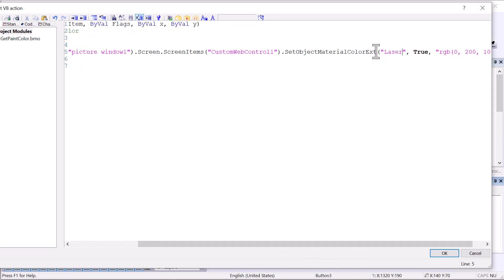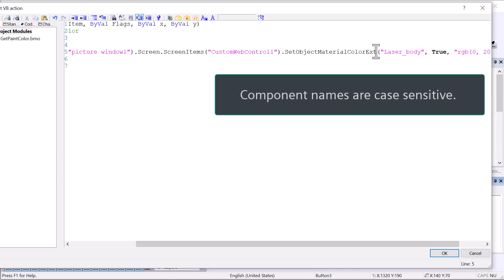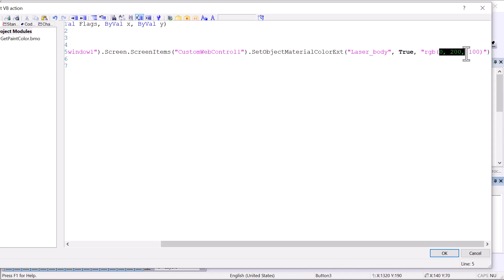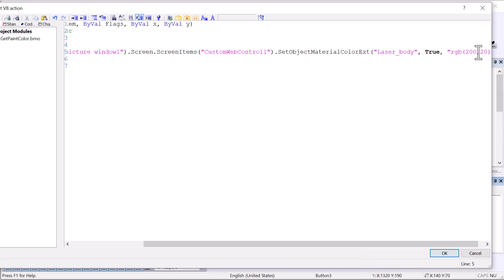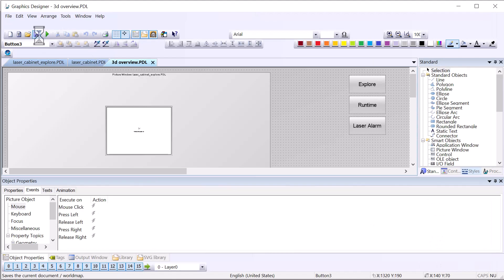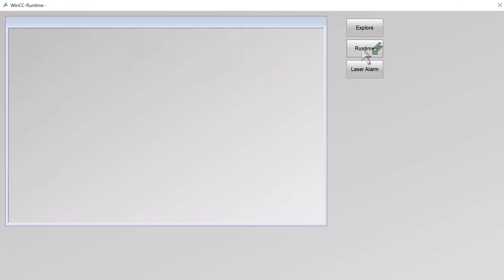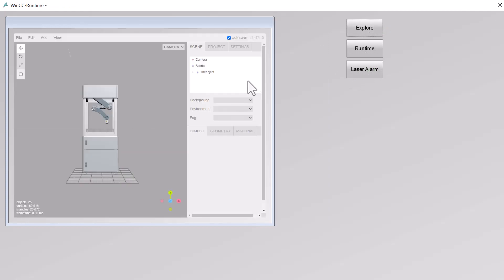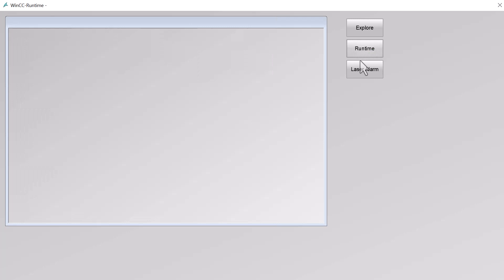I'll use the object picker — we're on the 3D overview screen, it's picture window one, and this is the custom web control showing the 3D object. Pro tip: this will only work if you're referencing a control that is in runtime mode, not explore mode. So laser cabinet is the screen and we want 'custom web control one.' That gives us a reference to our 3D control. We set the object to 'laser body' — another pro tip: you've got to get the case right, since I spent a few minutes wondering why it wasn't working because I had the B capitalized. RGB is 200, 20, 20. We'll test in runtime: clicking the button works.